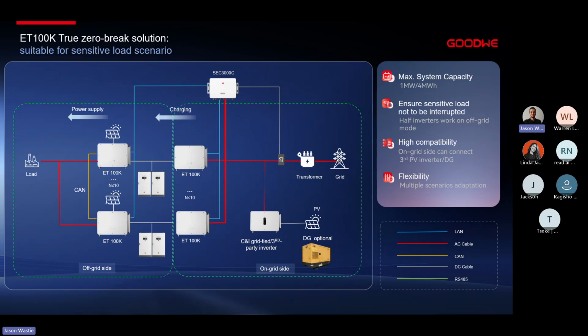How we do this is by having on-grid inverters connected with your AC from the grid, as well as off-grid inverters, with those two inverters connected to the same battery stacks. Your third-party grid-tied inverters, whether they are GoodWe or third-party, will connect up into your ET100 inverters, and the ET100 inverters will discharge power or receive power from everywhere to charge the batteries, and those batteries will then discharge through your off-grid inverters out towards your loads. Meaning, regardless of whether we're on-grid or off-grid, the entire solution will be able to operate.